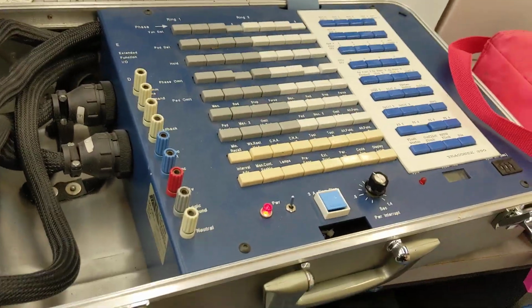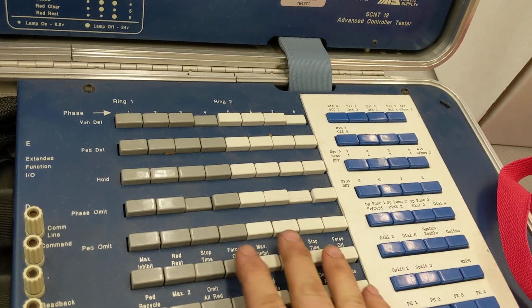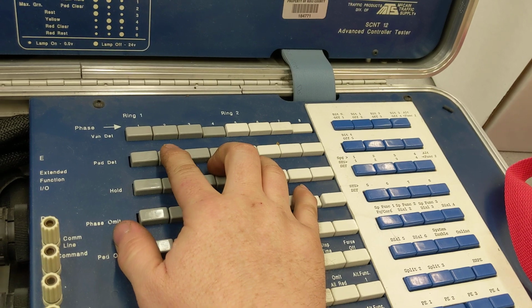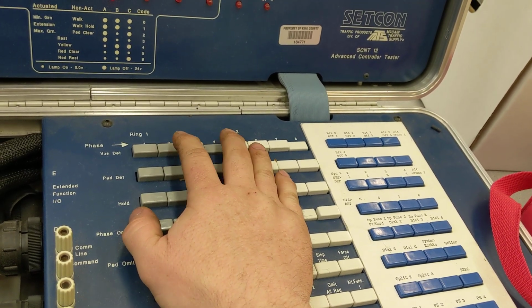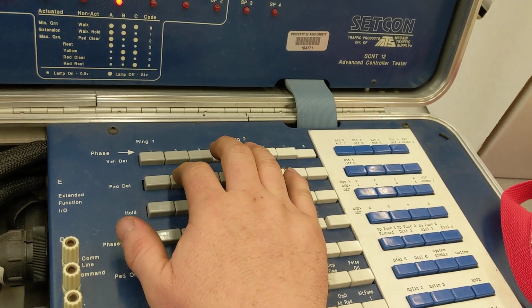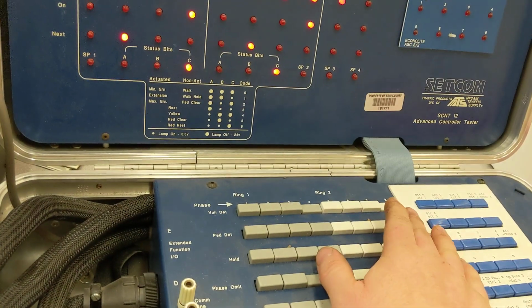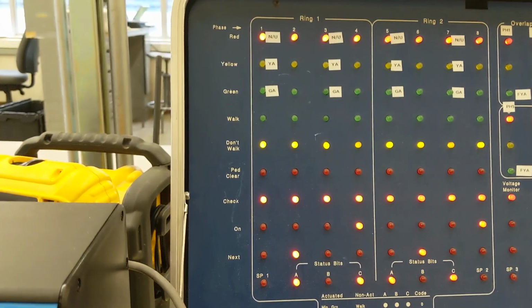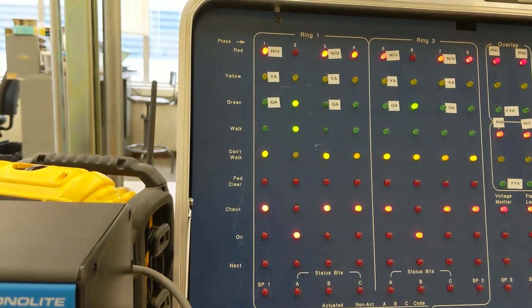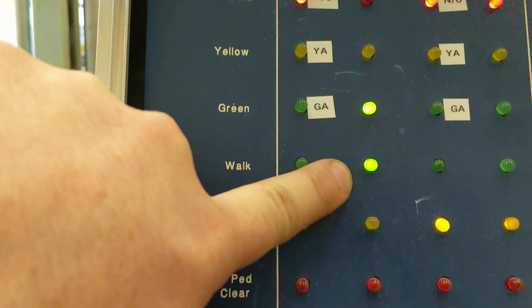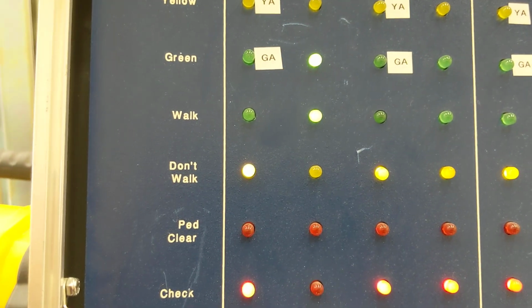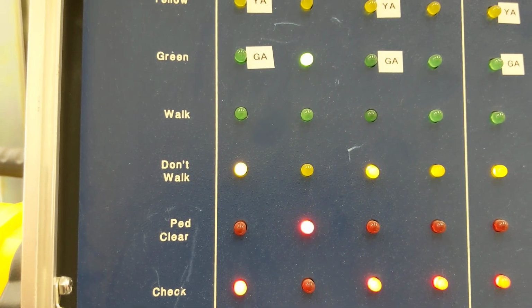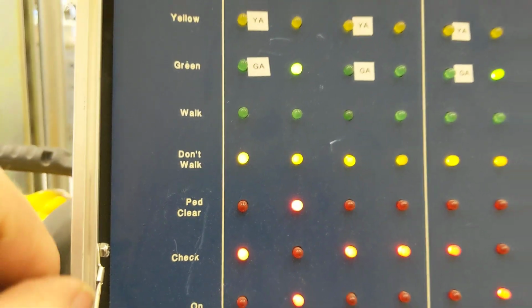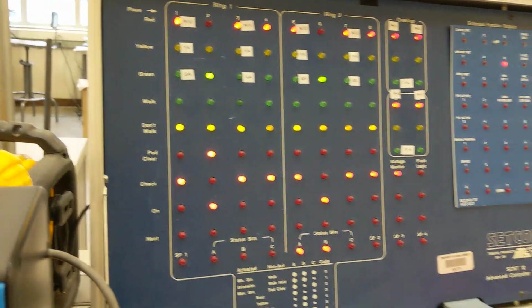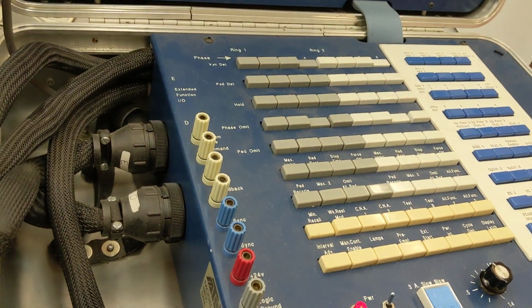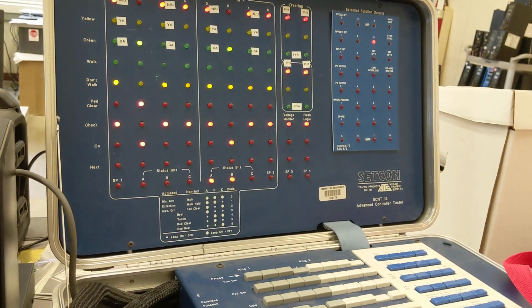And here, just to show you a little bit more about this briefcase tester, which is actually kind of an older piece of equipment, although I do believe they still make them. I can put in calls, phase calls, so I can put in a PED detector call, and right now you're going to see the PED is now serving, walk is serving, and now after the walk phase is up, now the don't walk is blinking. So we are just testing this controller, and this is one of the tools that I like to use on a regular basis.